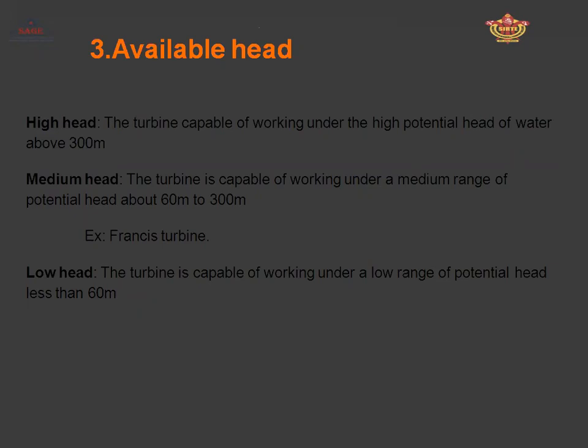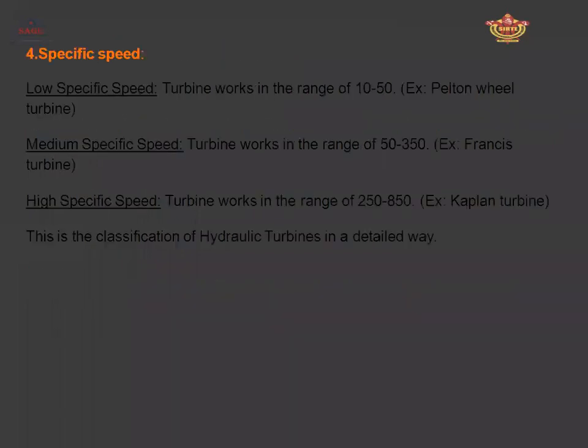The low head turbine works at heads below 60 meters. Regarding specific speed classification, there are three types: low specific speed, medium specific speed, and high specific speed. The low specific speed range is 10 to 50, and the Pelton wheel turbine falls in this category. The medium specific speed range is 50 to 350, and the Francis turbine is an example. The high specific speed turbine corresponds to the Kaplan turbine.